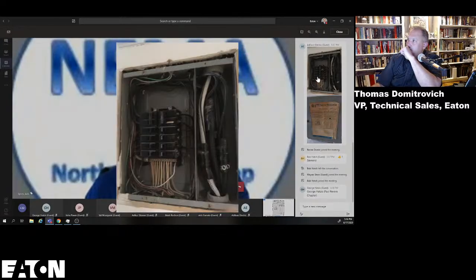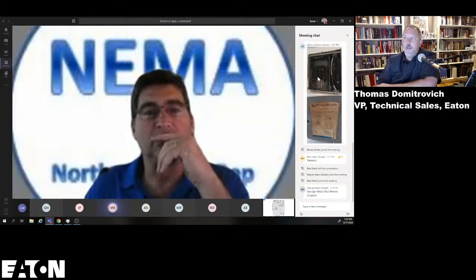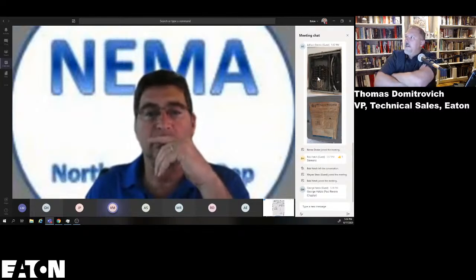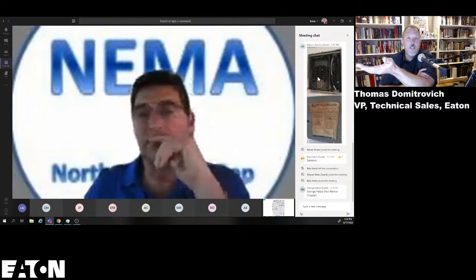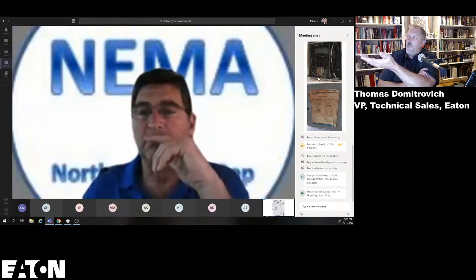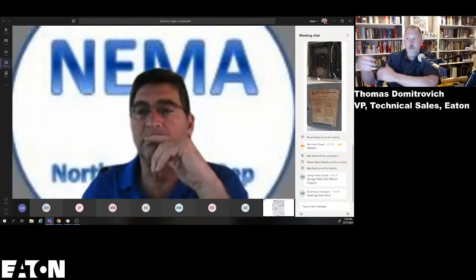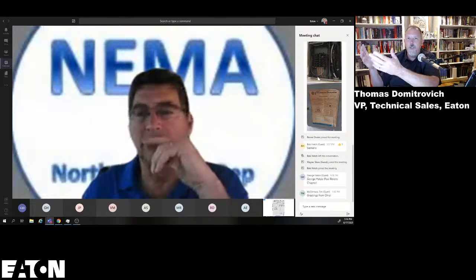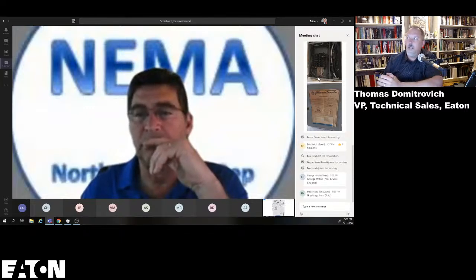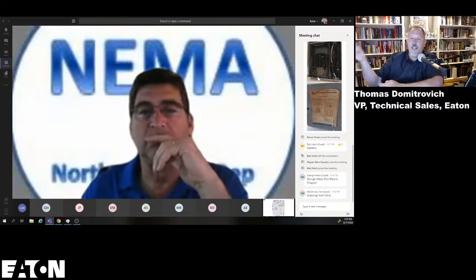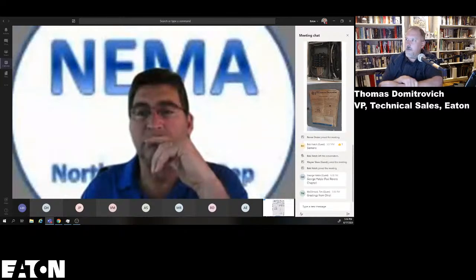Okay. And why is that? Why don't you just put an arc fault outlet in at the beginning of the source? Yeah, you could do that too, Val. You could put a receptacle right outside there and feed that through. And the reason, Jack, is that with the classified program, you're testing with other manufacturers' panel boards, basically product that's on the shelves. We're not going to go back and do a classified program with a product where, I'm not sure who owns ITE these days, but I doubt they're making those panels. Are they? Siemens owns ITE.